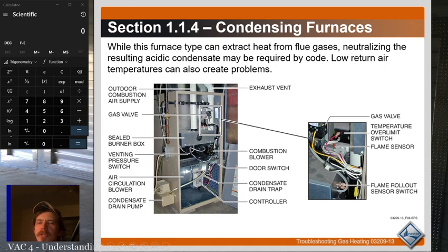You have the primary heat exchanger, which is the same as every heat exchanger in every furnace, basically, right? Then you have a secondary heat exchanger where the condensate and the flue gas goes through to extract more heat out of it. Typically, this is going to require a stainless steel or a PVC vent because the condensing flue gas will corrode steel, right? It's going to eat through the steel pipe. So the telltale sign that you have a condensing furnace is going to be the PVC or stainless steel piping coming out of it, and you're going to have two heat exchangers, a primary and a secondary, and they will need a condensate drain in heating. All right.